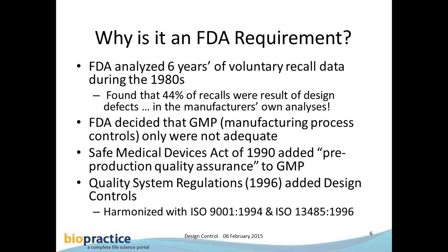It's an FDA requirement because FDA analyzed 6 years of voluntary recall data during the 1980s. So this is old data, but it was what FDA had at the time. Remember, the medical device amendments were only published in 1976. Before that, there were no GMP complaint or reporting requirements for medical devices. So after about 10 years under the medical device amendments, FDA took a look at the last 6 years of voluntary recall data and found that 44% of recalls were the result of design defects by the manufacturer's own analysis.